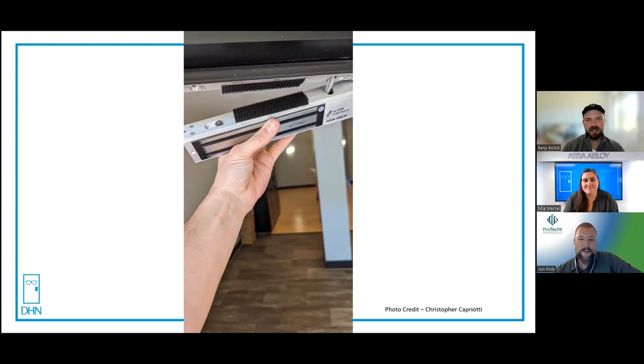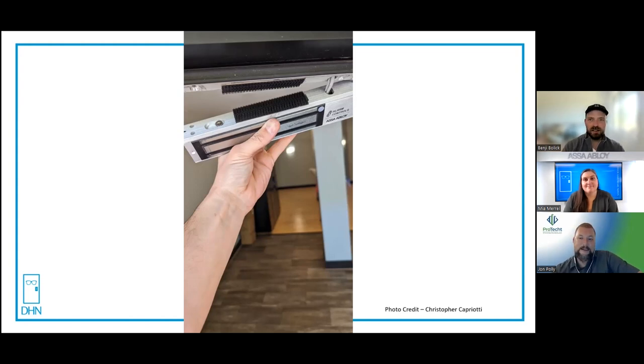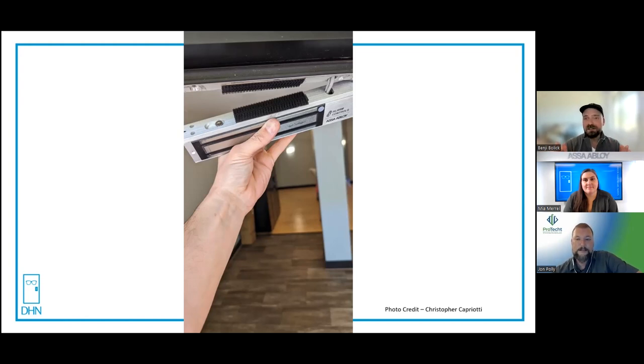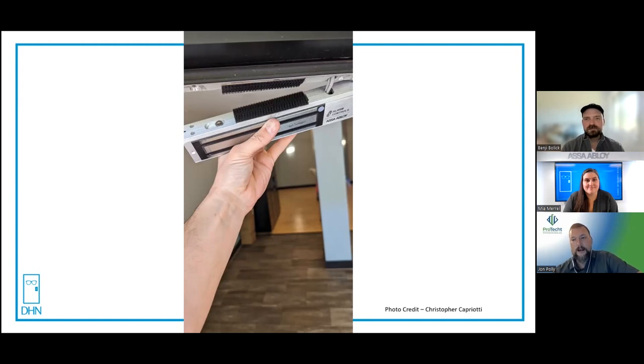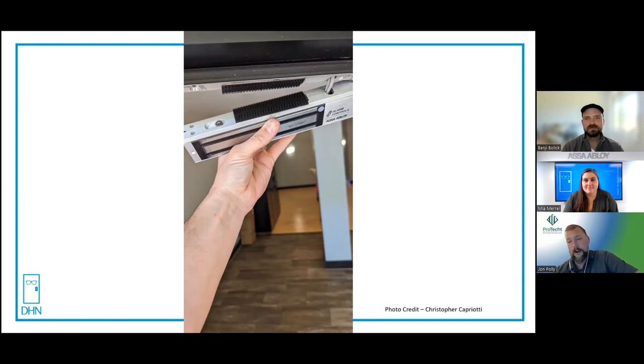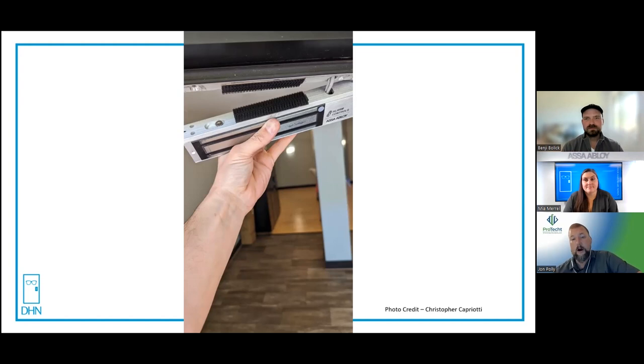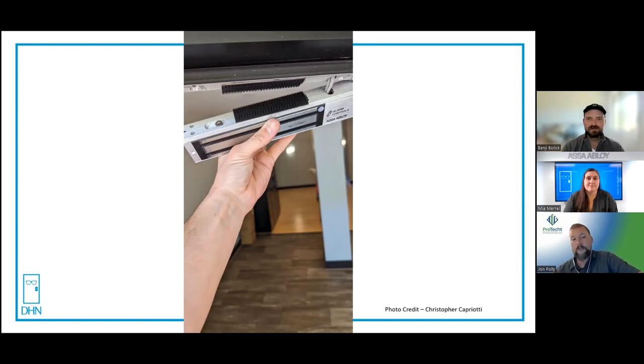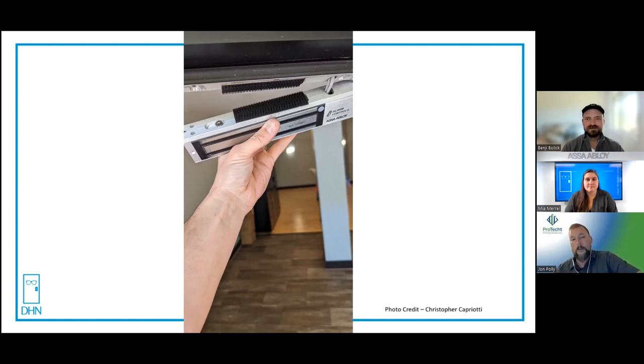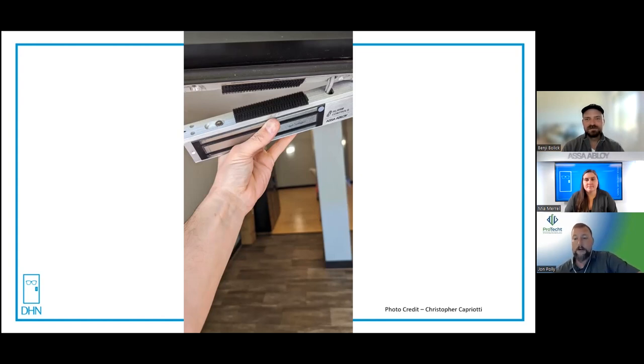When you're dealing with mag locks, that brings a whole other level of life safety codes involved. Mag locks can be tricky. A lot of integrators love going to mag locks because it's supposed to be a simple install and less expensive to add access control. But if you're not careful, you can get in really big trouble. It's got to have an automatic and a manual release, it's got to break power locally at the door as well as at the panel, it's got to be tied into a fire alarm panel. Now you've got the fire marshal that has to be involved. So a lot of companies don't want to take the risk of a mag lock and code compliance. I typically try to go away from mag locks if I can.